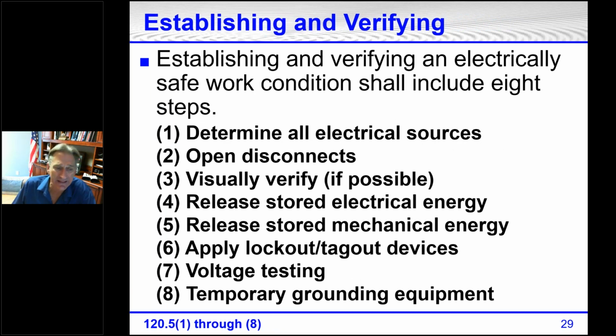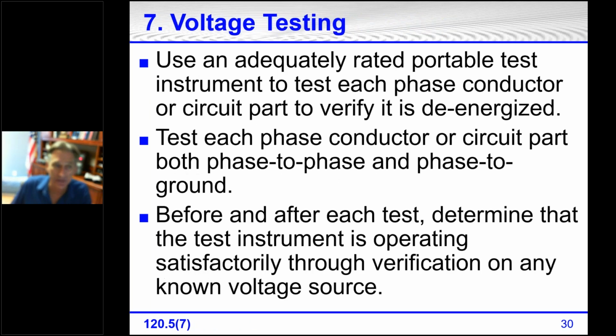Now, we don't have time to look at all these. Let's look at number 7, testing for voltage. Number 7 says use an adequately rated portable test instrument to test each phase conductor or circuit part to verify it's de-energized. Test each phase conductor how? Phase to phase and phase to ground. Some people refer to this as live-dead-live testing.